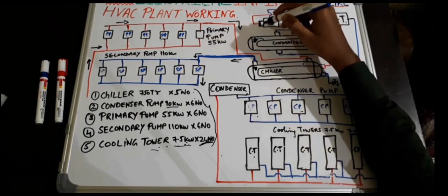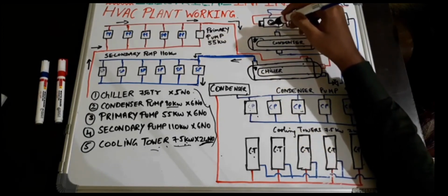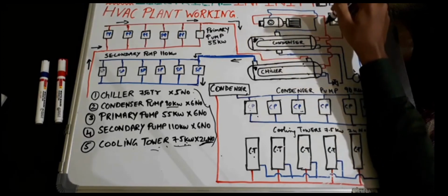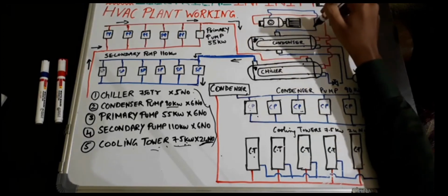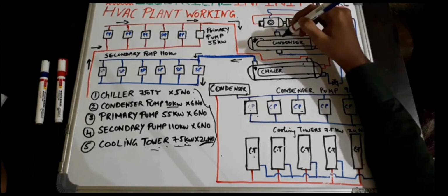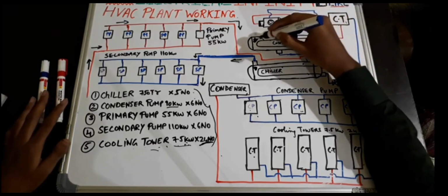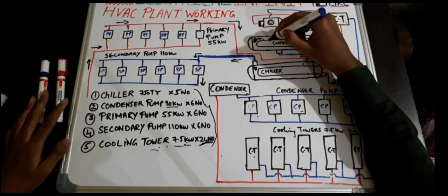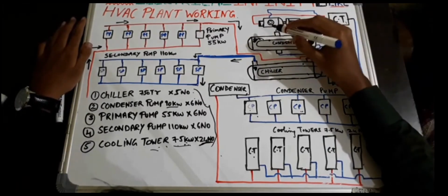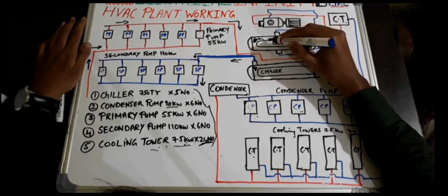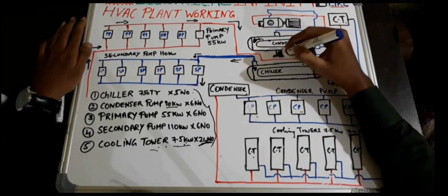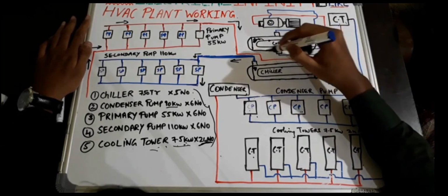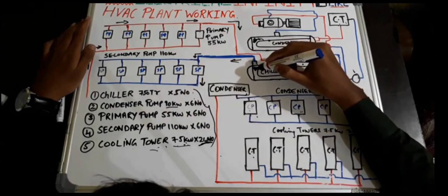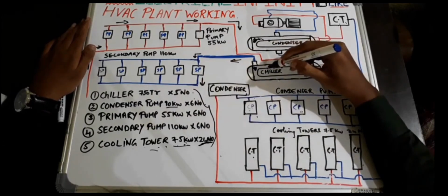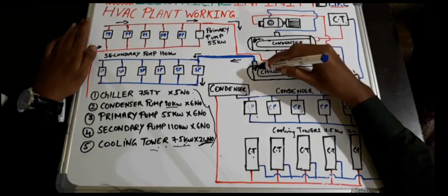The compressor again compresses the high temperature refrigerant and sends it to the condenser, as you can see here, for cooling of refrigerant, where heat exchange takes place between the refrigerant and the cool water of the cooling tower. So here you can see the heat exchange takes place in the condenser between the refrigerant present in the shell type and the cooling water present in the tube type, whereas in the chiller the refrigerant is present in the tube type and the cooling water of the entire building is present in the shell type.